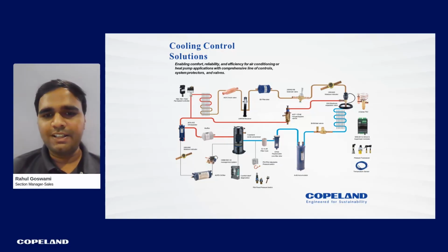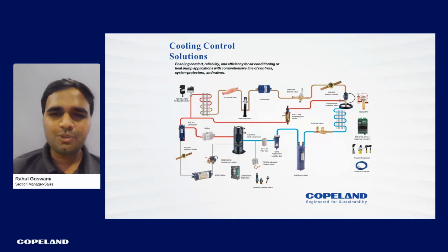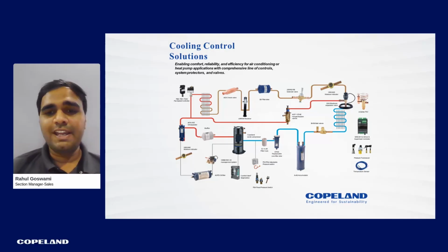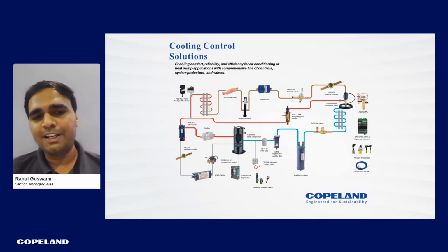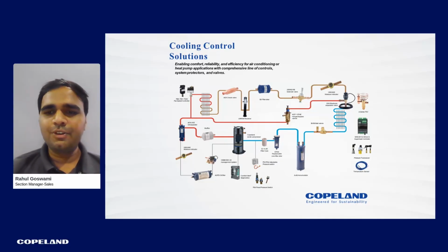Then after that we have the fan speed controllers, which are used to control the speed of fans in the condenser as well as in some cases of evaporators. And then we have check valves, liquid receivers, filter dryers, and then solenoid valves. We have expansion valves, both thermal expansion valves as well as electronic expansion valves. And we also have the accessories which are required for the electronic expansion valve. We will go into detail in further slides for that.